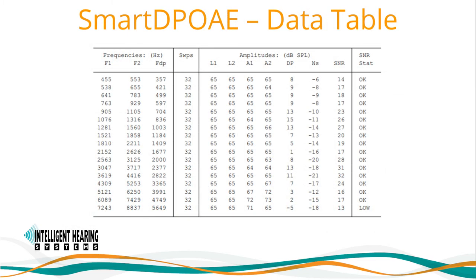A result data table will print out with every DPgram listing the F1-F2 frequency pairs along with the DP frequency, total number of sweeps acquired, desired output intensity levels L1 and L2, and the actual output levels. Results will be shown as average DP amplitude, average noise floor amplitude, the signal-to-noise ratio, and whether the SNR criteria was met. In general, DPoAE results are best when normal hearing is defined between 20 and 30 dB HL. Absent responses are typically found at thresholds greater than 40 dB. DPoAEs can be used to predict magnitudes of hearing loss up to 60 dB HL.